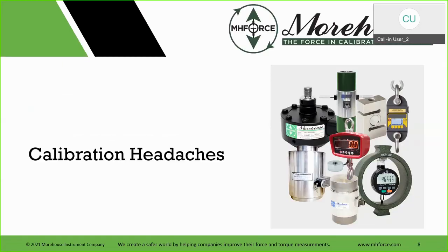We talk about calibration headaches. Manufacturers have not standardized their instruments, right? So if you buy a 10,000 pound load cell and somebody else has a 10,000 pound load cell, there might be different thread sizes. One might be 5/8-18, one could be 1¼ inches, all variables: the bottom adapters, the hole size on tension links, everything. Nothing is really standard. And what did the manufacturer do to test? How are they getting their specification? When they say something is accurate to X, how are they getting it, right? Is this achieved once, never repeated? Is this a conservative estimate? Is it just an estimate where they're taking averages, which some do?